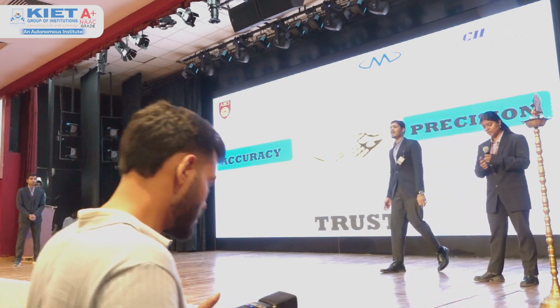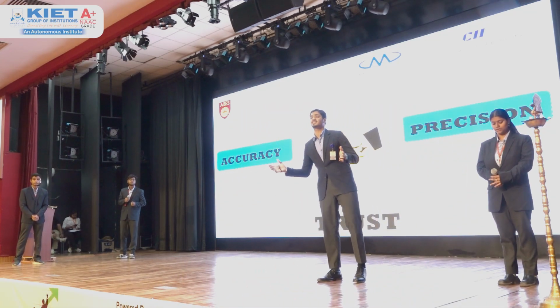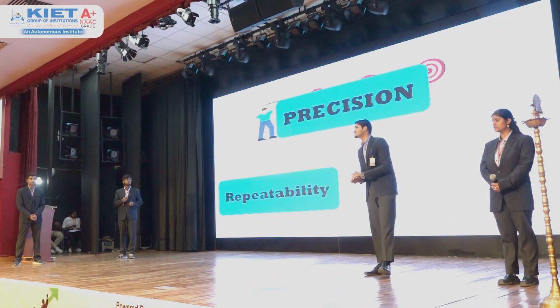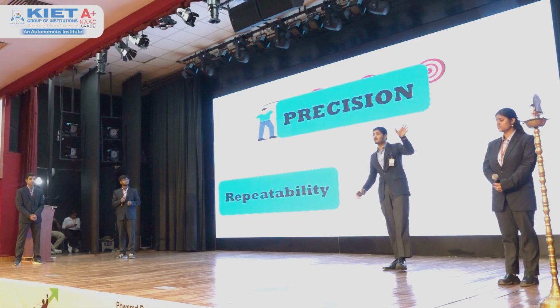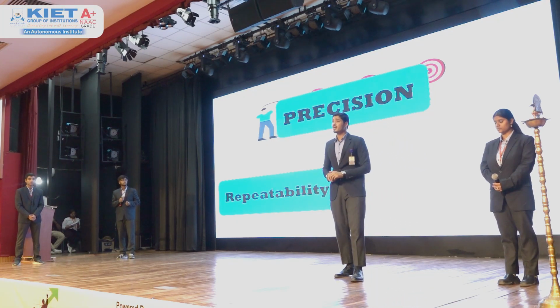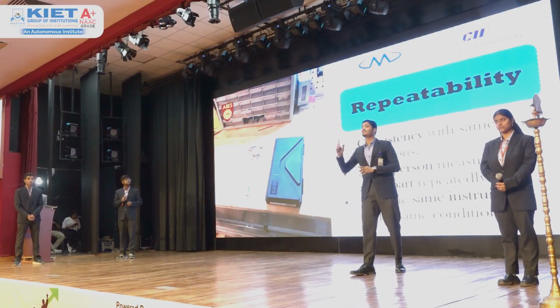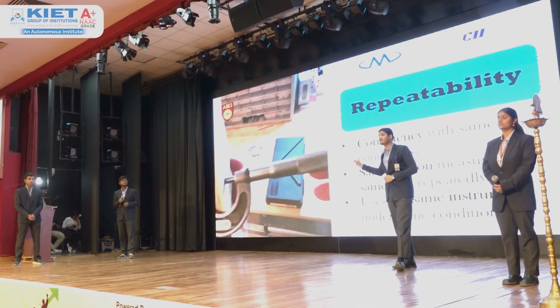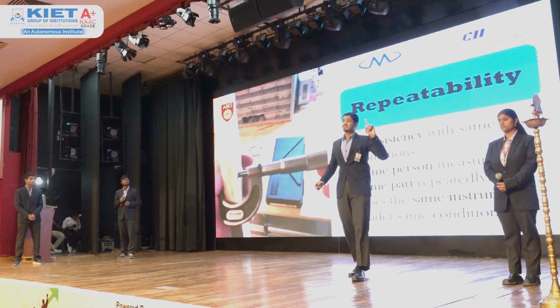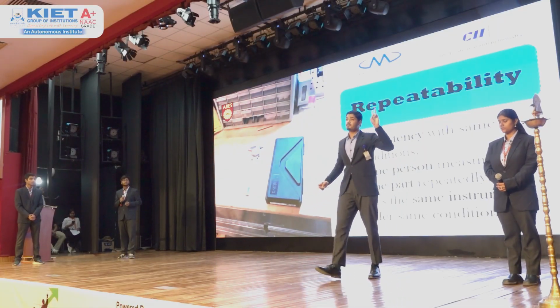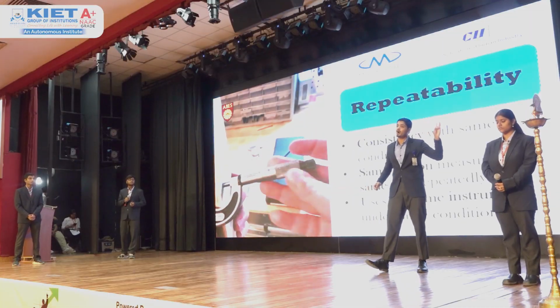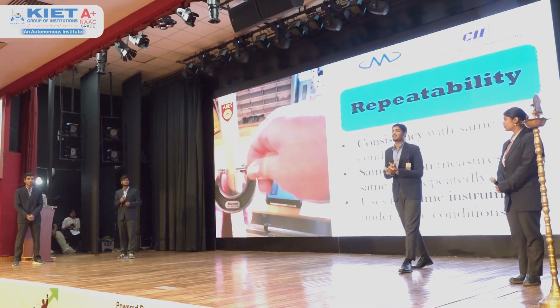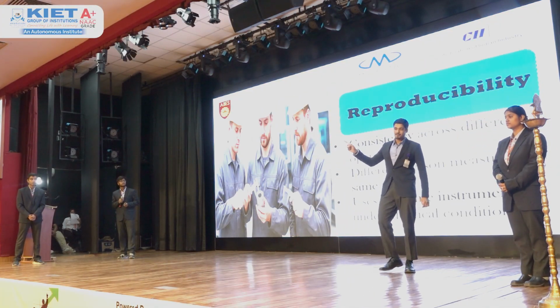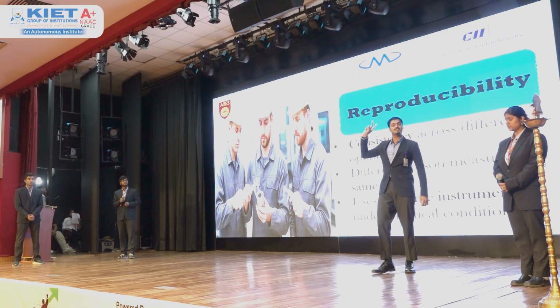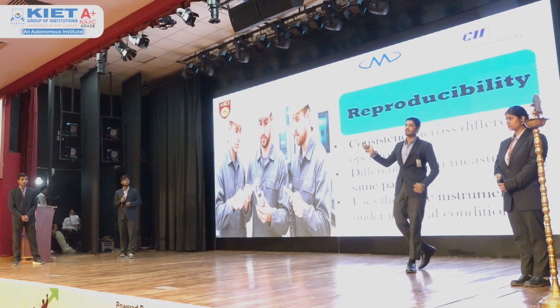If the answer to your accuracy or bias error lies with calibration, then how do we address precision? It is the consistency of repeatability and reproducibility. Repeatability stands for the variation in your measurement equipment, with the same equipment, the same part to be measured, and the same appraiser. While reproducibility is the ability of appraisers to measure with the same instrument, the same product, and different appraisers.